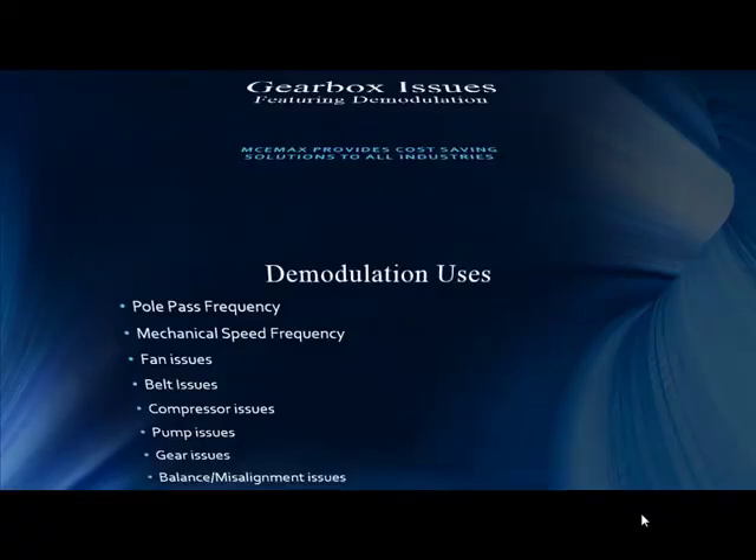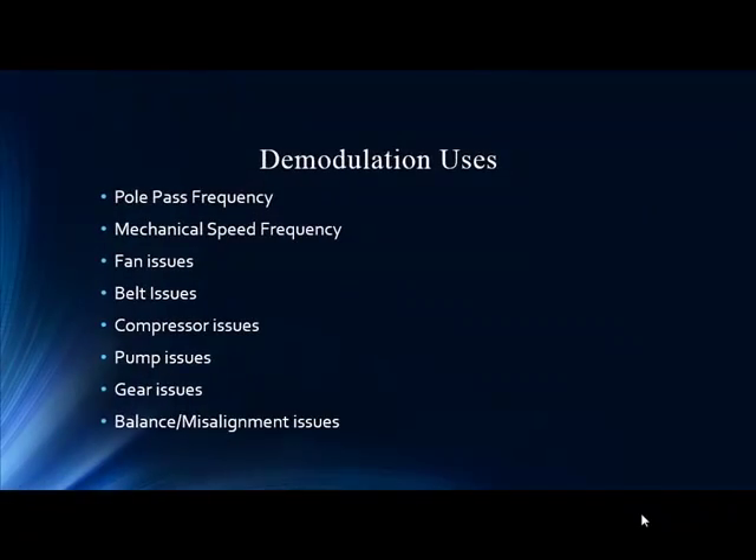We know demodulation for finding pole pass frequency and the mechanical speed of the rotor, but there's a lot more going on. Those first two are great for rotor bar and eccentricity, but all the other spectral peaks in the demodulation can be utilized for machine train analysis — fan issues, belt, compressor, pump, gear, balance, misalignment — all of those you can find with a little knowledge in the demod section.